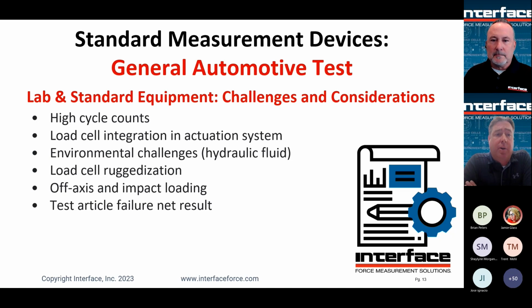Jeff touched on this in the prior slide, but load cell integration into the actuation system. How are you going to integrate it? Does your actuator have a male thread? Is it female thread? Is it horizontal? Is it vertical? How is that actuation string going to be supported if it's horizontal and you do not have the test underway, or it's not in place? Do you have straps in place to minimize bending moment on the load cell? A lot of different concerns around that.